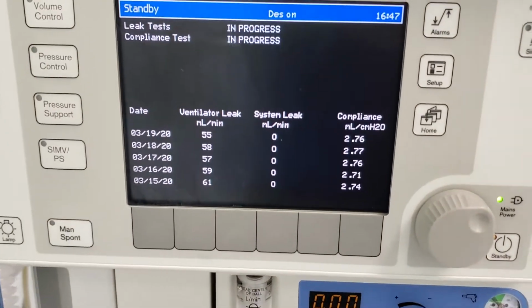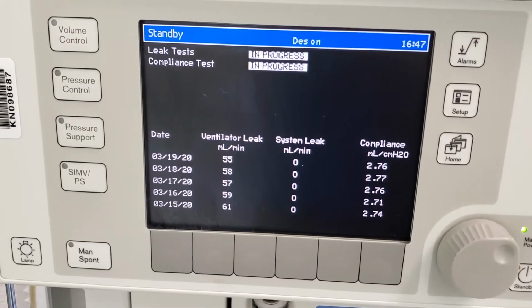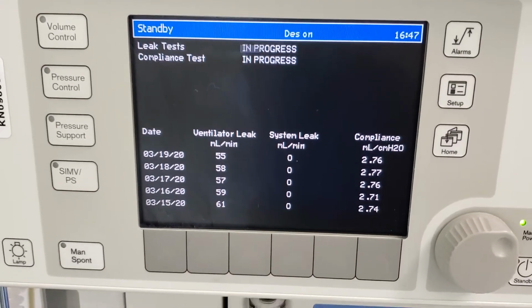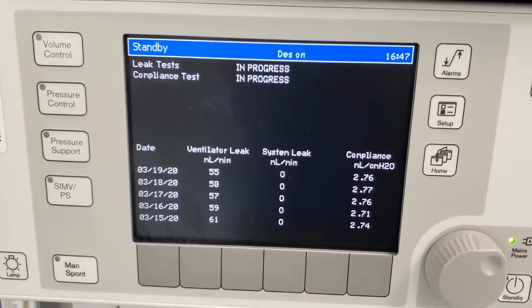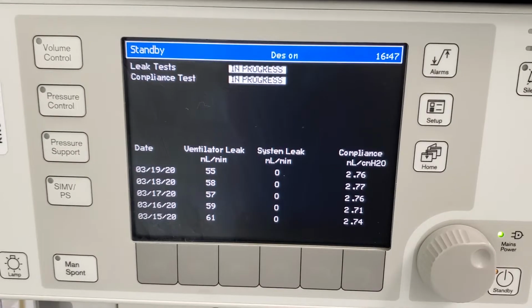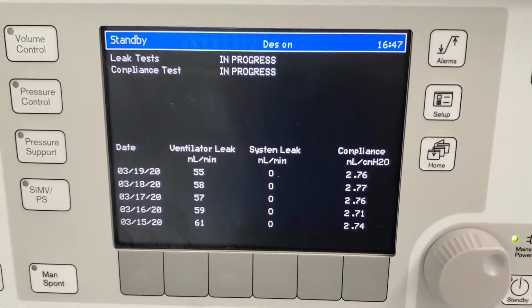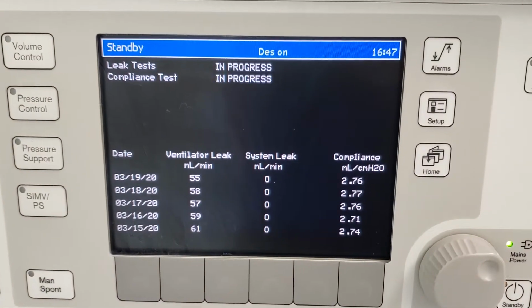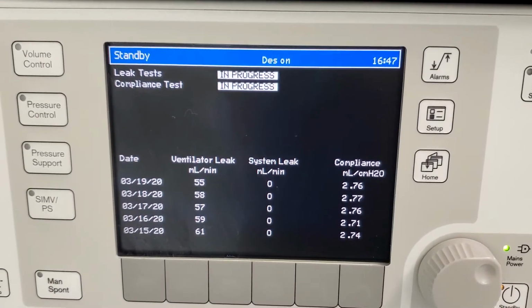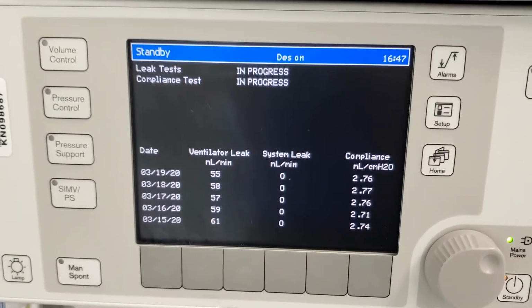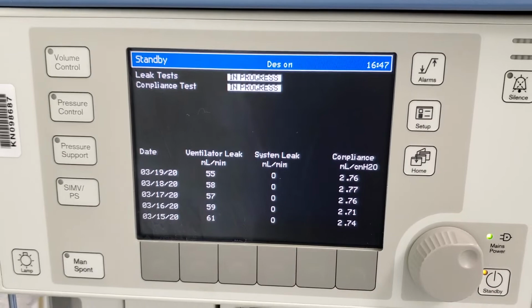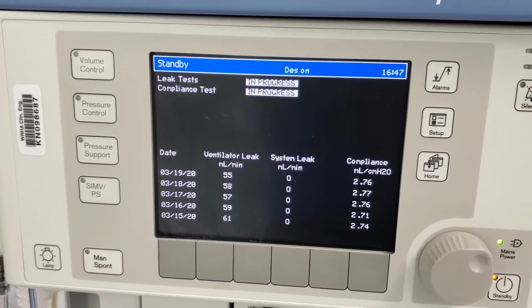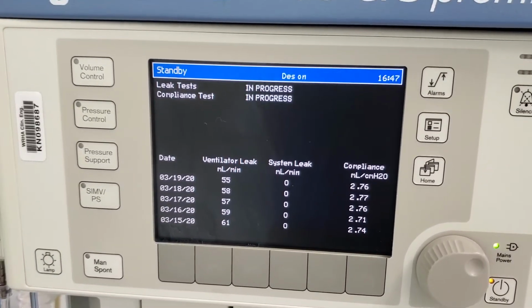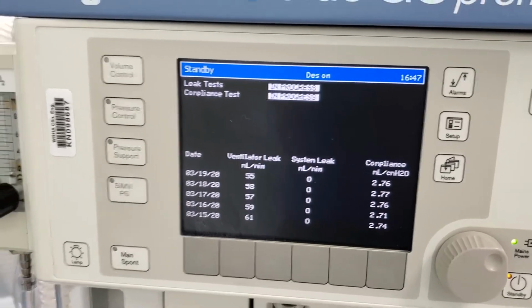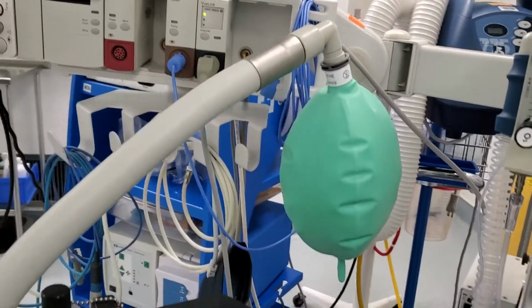You can see the last 5 tests that have been done. If there is a leak, it will basically calculate it into ventilator leak or system leak, and then it also measures the compliance of the circuit. So you can see the last 5 compliances are very similar. If we were doing more with pediatrics, where the compliance, if it was different between circuit, that could technically affect our tidal volume delivered to the patient.